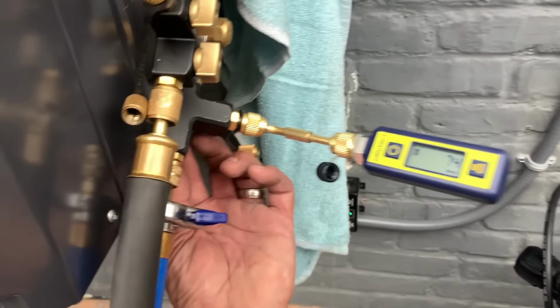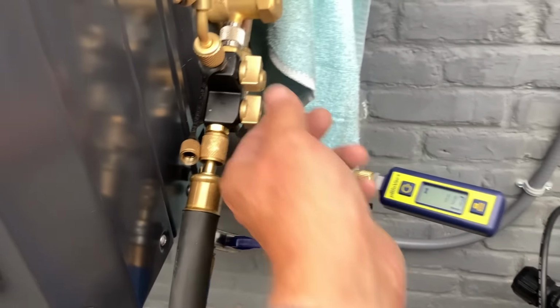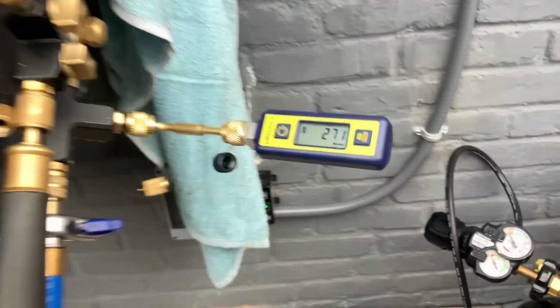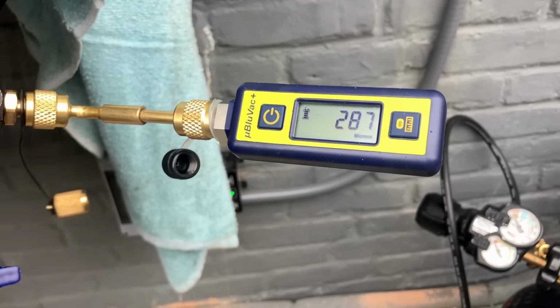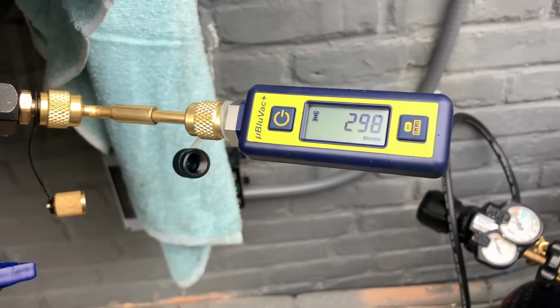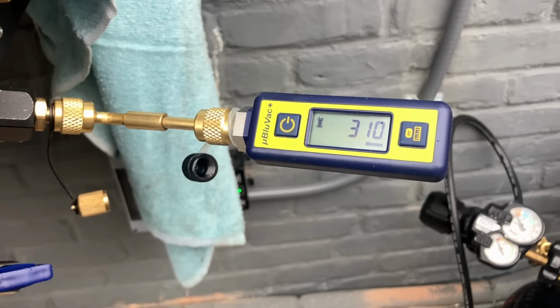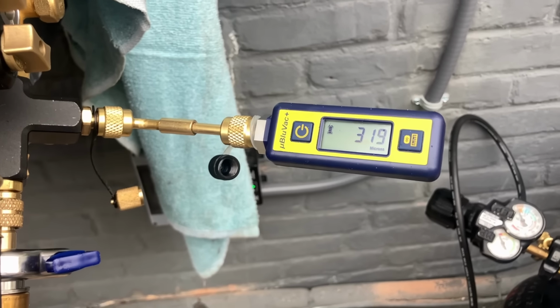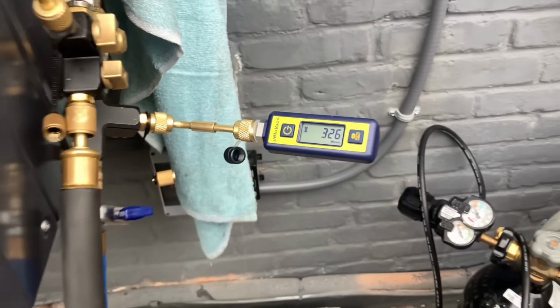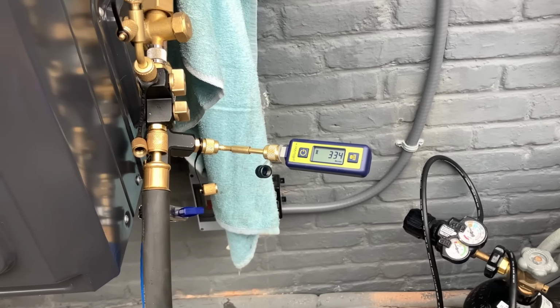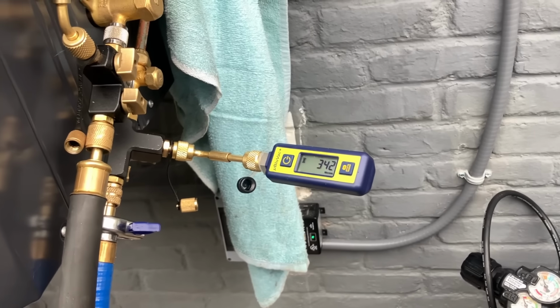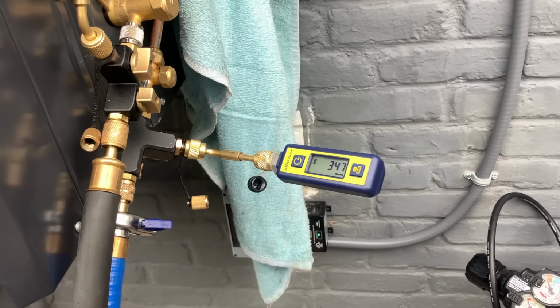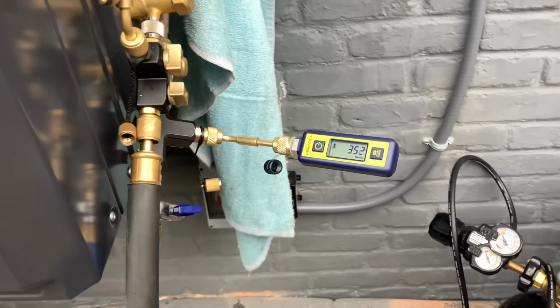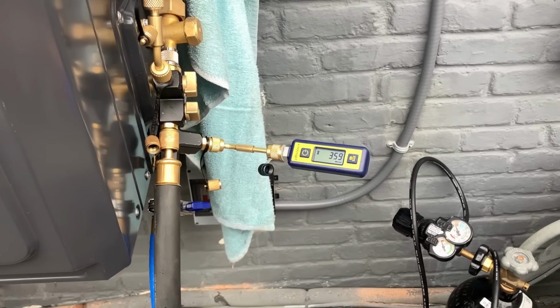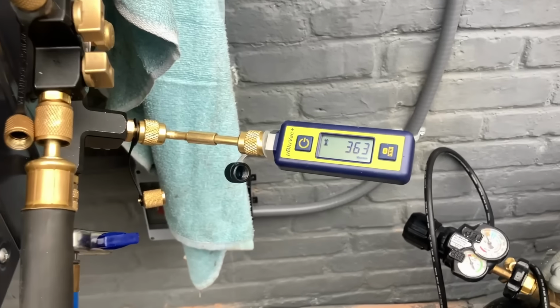74 microns, let's close that, let's close this. We want that to start dropping. We want it to stop and then start dropping. If it doesn't, that means we still have moisture in the air, in the line set and evaporator.